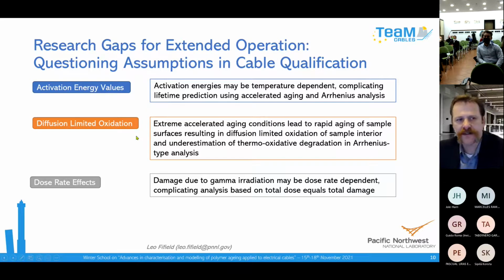One of the questions is about activation energy values. The way you put 40 years of age on a cable before you test it is, if the main degradation pathway is thermal degradation, you can just apply a higher temperature and it ages faster. You use an Arrhenius process to calculate how many equivalent years it represents when you do that laboratory aging. But the question is that the activation energy that you determine through a series of elevated temperatures might actually be temperature dependent.